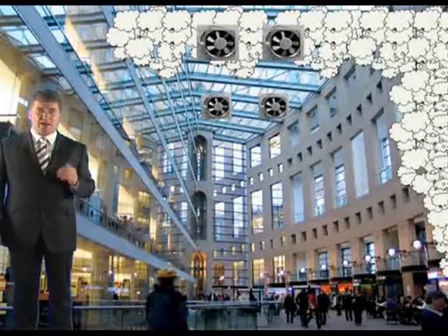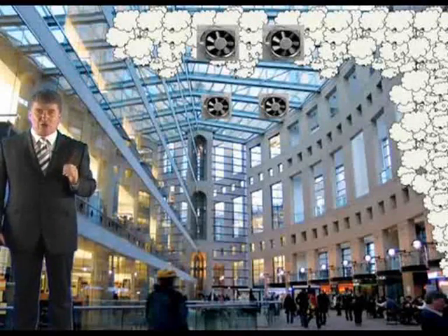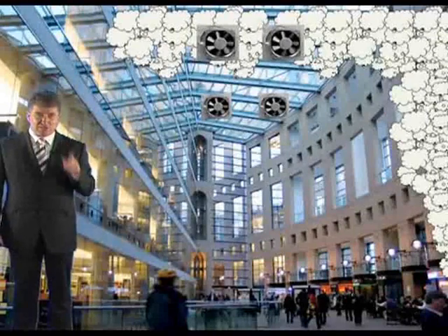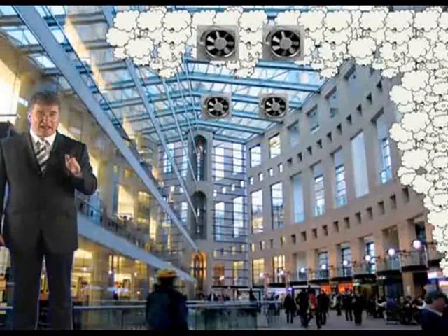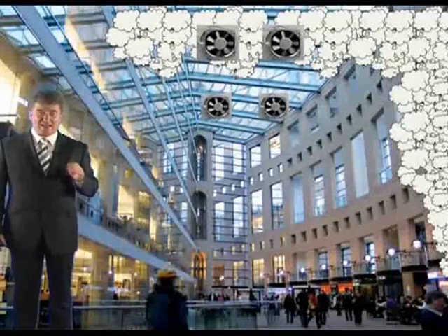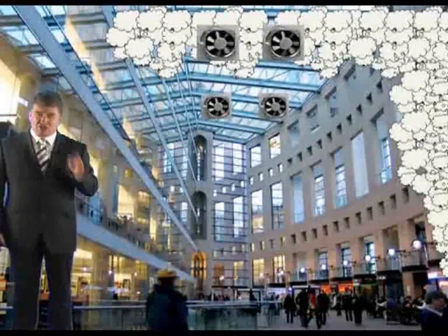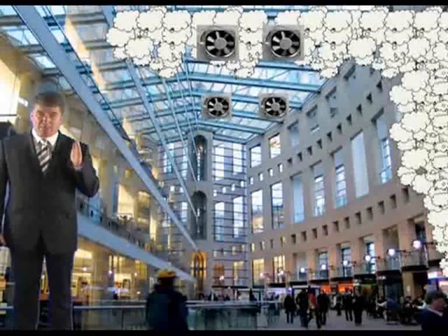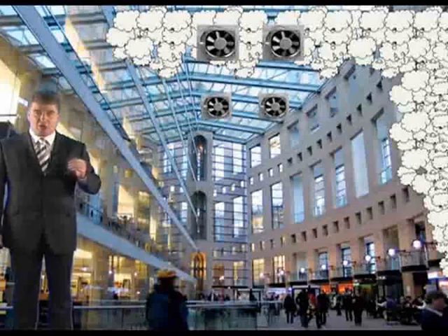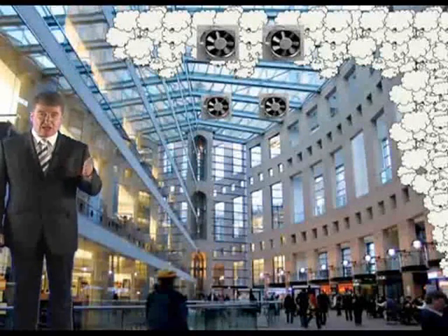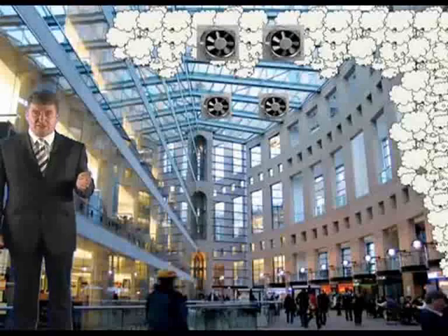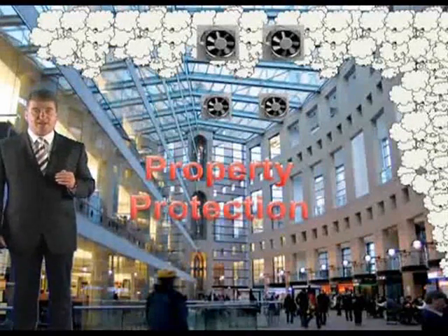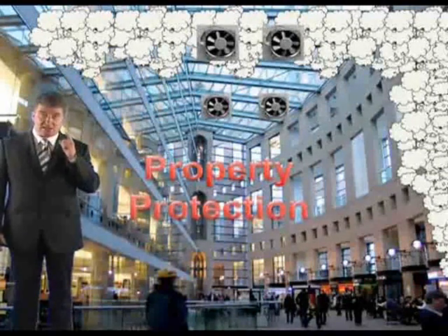Now, in situations where smoke from a fire in a single shop unit could spread rapidly via the malls through the entire centre, a smoke exhaust ventilation system in the mall is essential to ensure that escape is unhindered, by ensuring that any large quantities of thermally buoyant smoke remain above the people who may be escaping below it. Therefore, in shopping malls, the primary role of the smoke control system is one of life safety. Secondary is property protection and access for the fire service. The primary role is life safety.